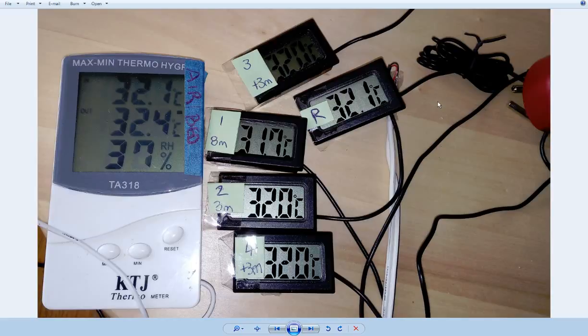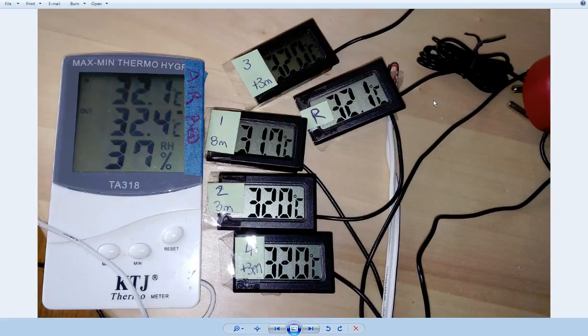You can see here what I'm actually doing is what I call benchmarking. After I've extended the wires I've hooked them back up temporarily. You can see under the one that says R there's some little wires and a bit of tape sticking out. After I put the extensions on I benchmarked them back against R. The one with R written on it is my reference thermometer. I picked a thermometer that seemed to be close to the large in-out thermometer that you can see, and I haven't extended that R or reference thermometer.